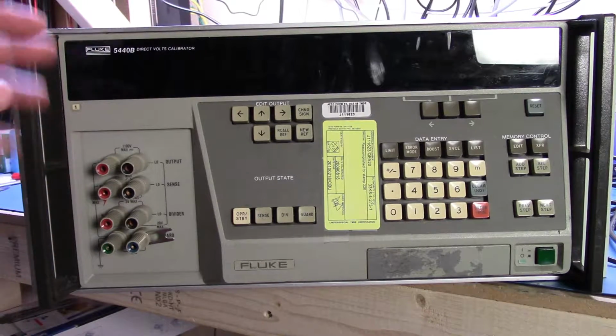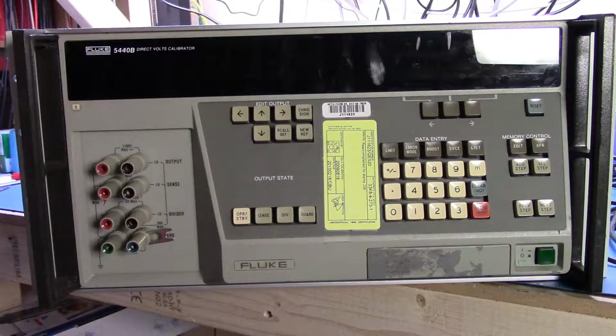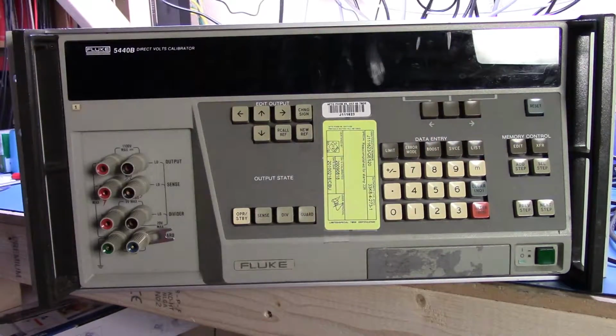These units are pretty cool because they let you control the calibrator to tell you the error percentage, or parts per million error, of the device you're calibrating, as shown over here.